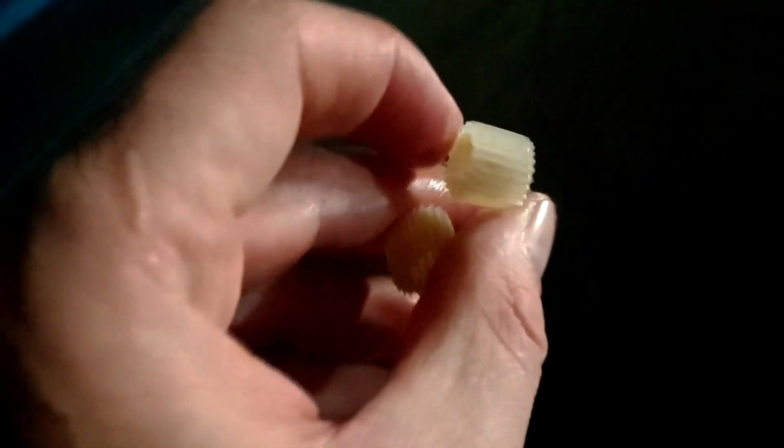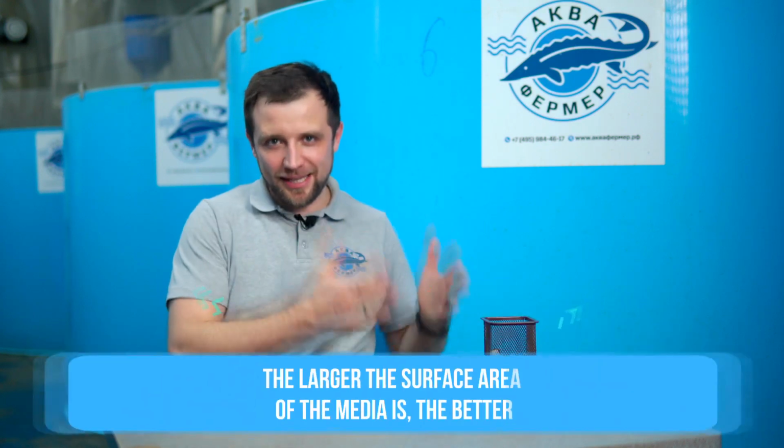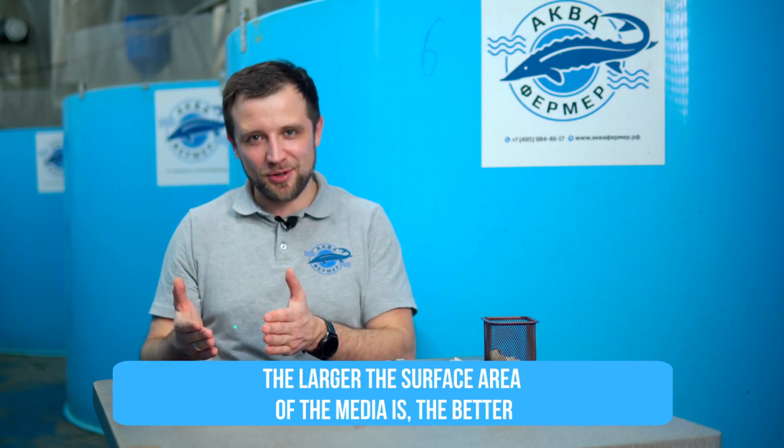Imagine that you have a biofilter. It is 1 cubic meter of bacteria settled on the entire media surface. The more bacteria colonies can settle on this media, the better it is. This is called the surface area. One type of media can have a surface area of 300 square meters per cubic meter, and the other can have 1000 square meters per cubic meter. 1 cubic meter here, 1 cubic meter there. And the difference is up to 3 times.